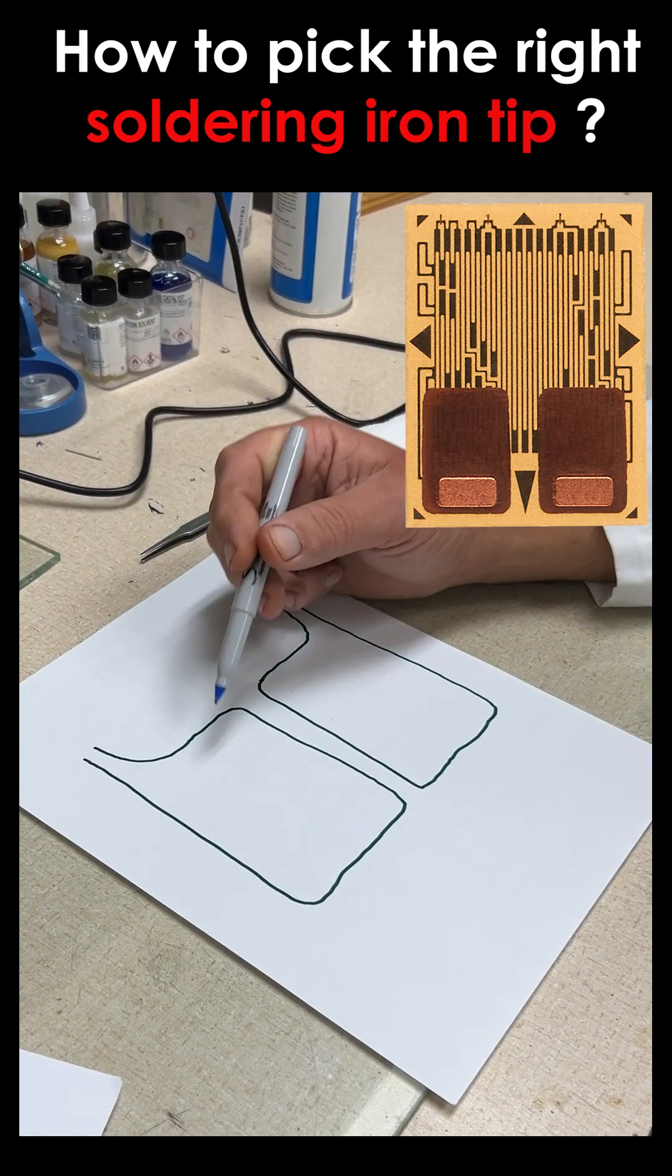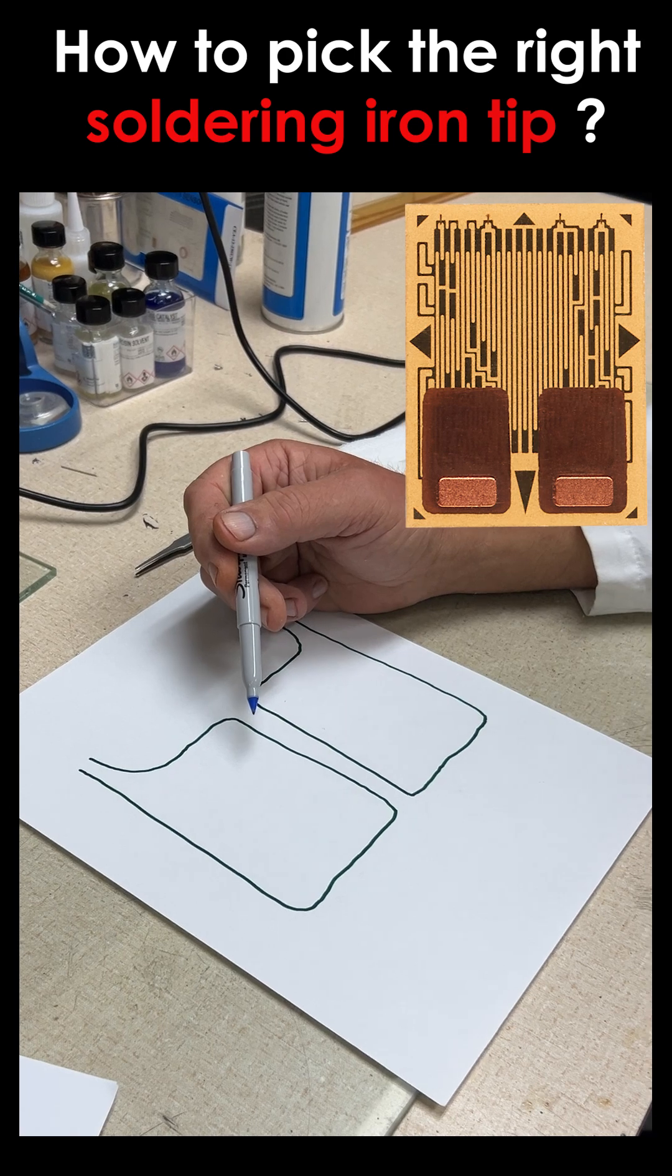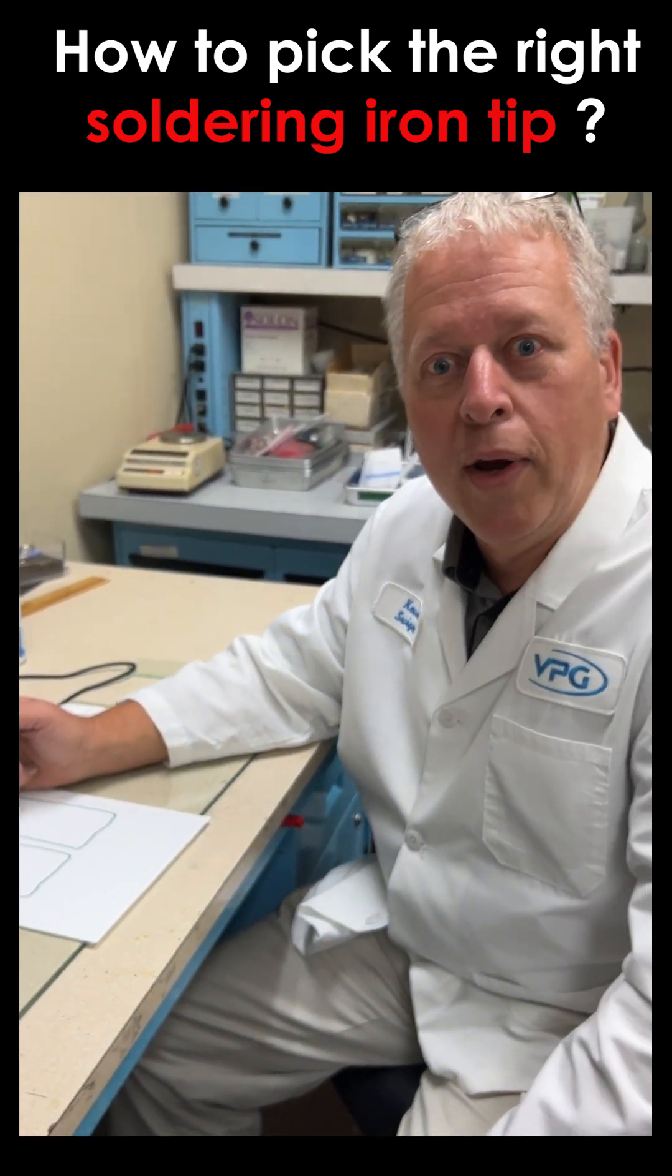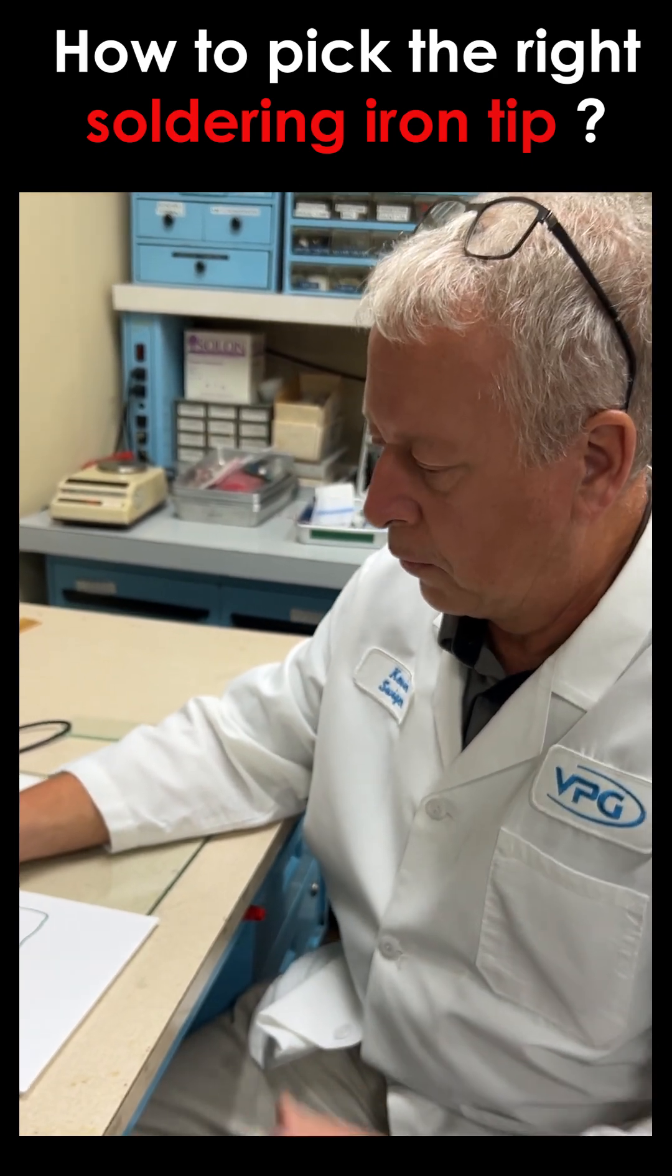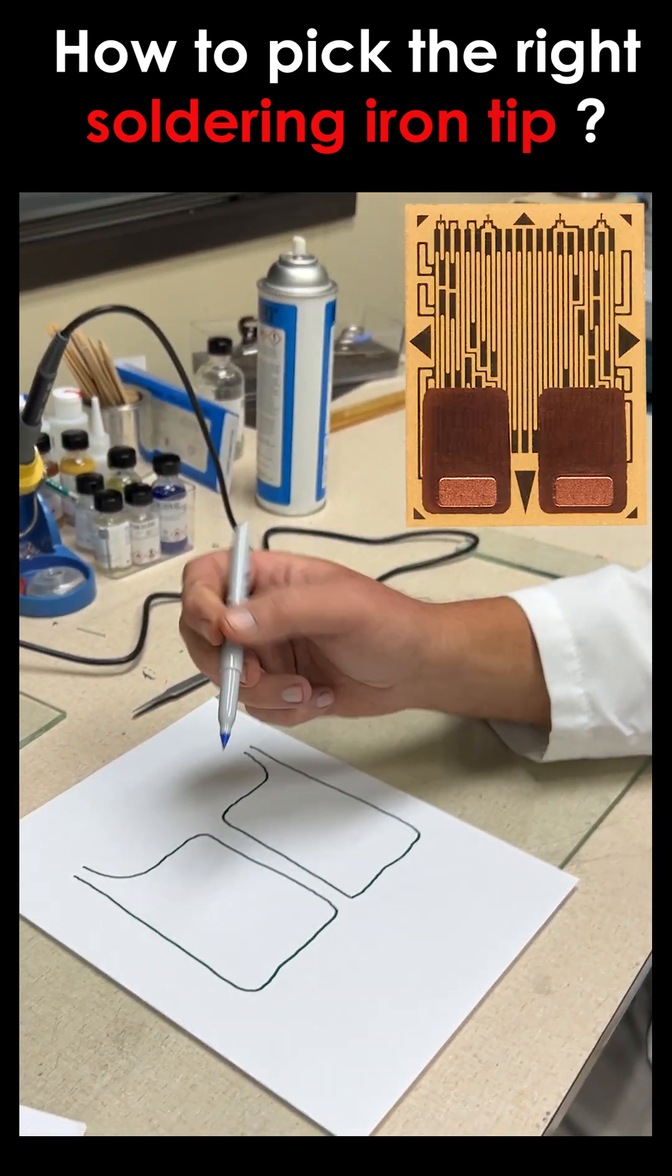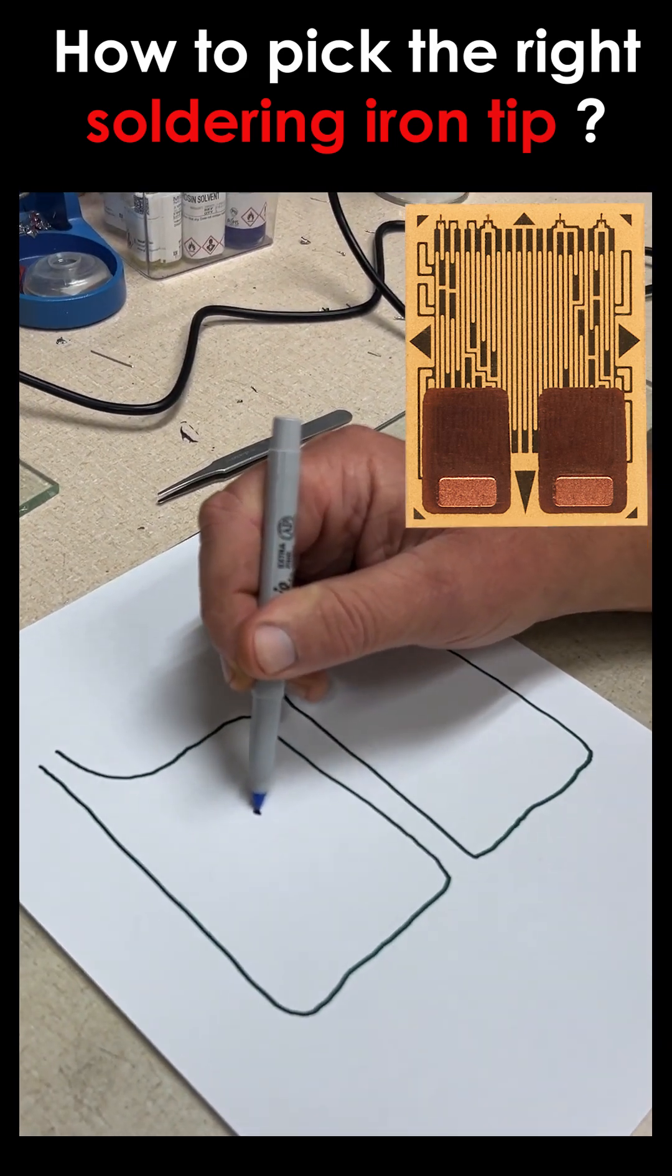So imagine that these are the two strain gauge tabs that we just looked at. Now, when people begin strain gauge soldering, their first inclination is to use a very tiny, sharp-pointed tip. And here's what can happen when you go down that road. Let's say this Sharpie pen is a sharp-pointed tip, and I touch the foil here at this surface right there. Point contact.